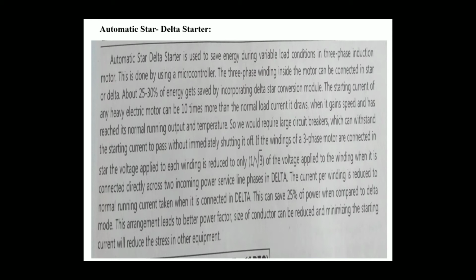If the windings of a three-phase motor are connected in star, the voltage applied to each winding is reduced to only 1 by root 3 of the voltage applied to the winding when it is connected directly across two incoming power service line phases in delta. The current per winding is reduced to the normal running current taken when it is connected in delta. This can save 25% of power when compared to delta mode. This arrangement leads to better power factor, the size of conductor can be reduced, and minimizing the starting current will reduce the stress on other equipment. This is the automatic star delta starter.